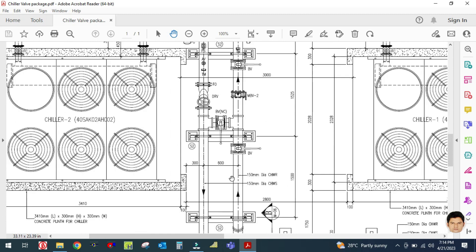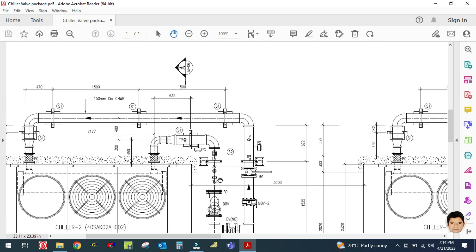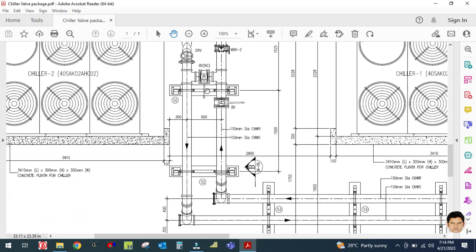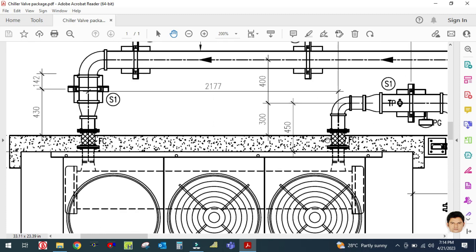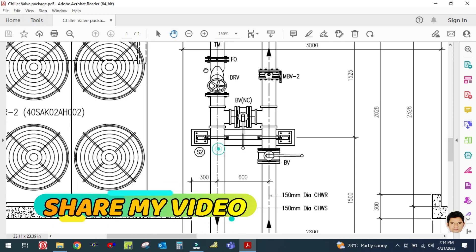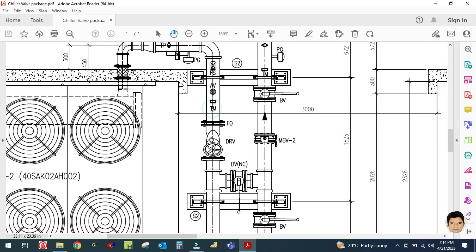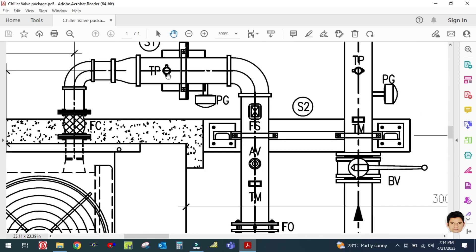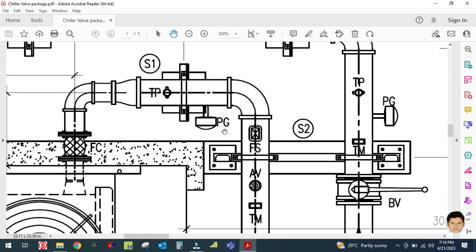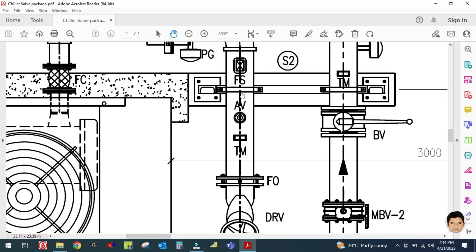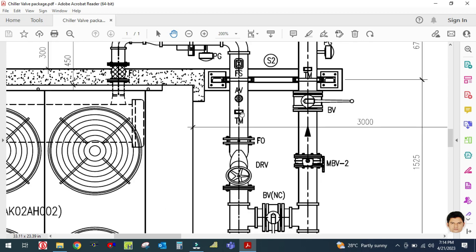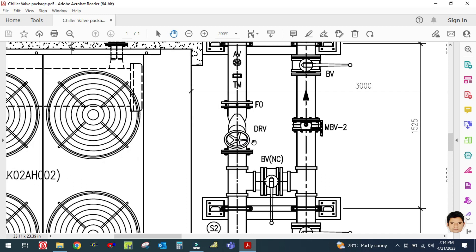This is your chill water return line. I will show you what accessories are used in both supply and return lines. First, in both supply and return lines there will be a flexible connector. After the flexible connector, in the suction and discharge lines there will be a double regulating valve (DRV). Before that there will be a test point, pressure gauge, and temperature gauge. TP is nothing but the test point, and AV is nothing but the air vent.